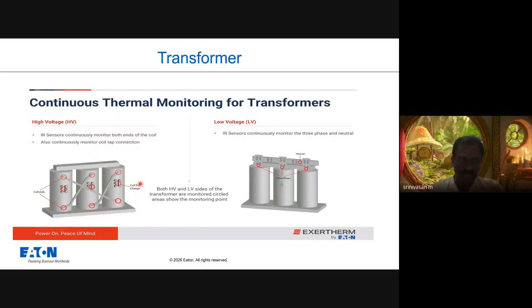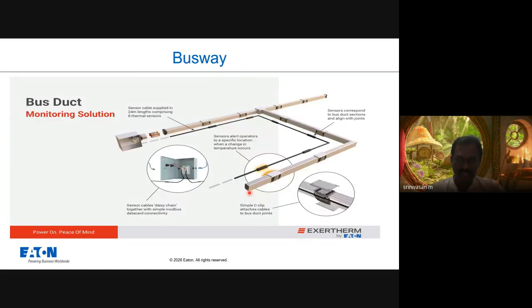You can also see examples of where we install the thermal point sensor in transformers, on both the high voltage side and the low voltage side. We can also have the sensors in busway systems. Wherever we have busbar joints and the external enclosure, normally either an aluminum housing or a sheet steel housing, at the place where the enclosure housings are joined we can place this thermal sensor, so that it can give the temperature values 24/7 to the higher level BMS or SCADA system through communications.